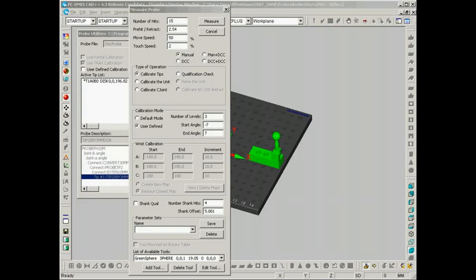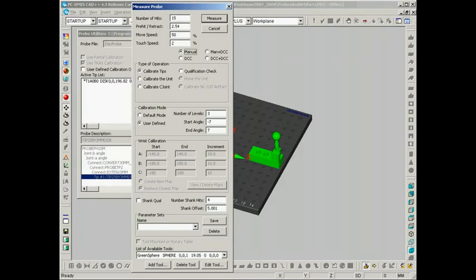So the next thing we want to do is go into the probe measurement dialog, and we want to change a couple of the parameters to suit this sphere. First thing we're going to change, number of hits. We'll put that at 15. And down here under calibration mode, I've toggled it to user defined, 3 levels, which will be 15 divided by 3, 5 hits per level. And here's the trick right here. Start angle is -7 degrees, end angle is +7 degrees. And then down here I've chosen my green sphere, which I've previously located with my normal spherical stylus. So the software can automatically go and measure this sphere without having to try to do any locating hits.